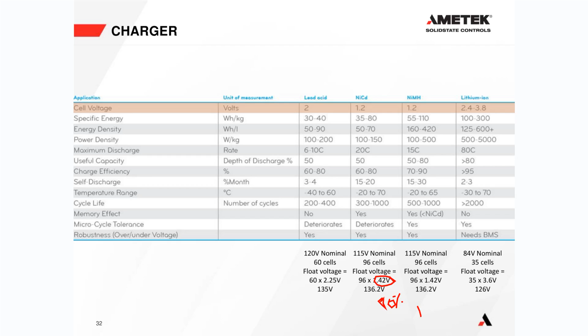A lot of people think that batteries just sit in the corner and do nothing. They're inanimate objects, but the battery is absolutely critical. We do a training class here. We've got one going on just now where the guys come in and our battery trainer goes over batteries, and they come out of that class thinking, wow, I did not know there was so much to learn about batteries, because even though they are just plastic inanimate objects, they are critical to the operation of the UPS. If you have a bad battery, it's not being charged correctly, it's being abused, then your UPS is useless if your battery is not going to provide the power necessary.